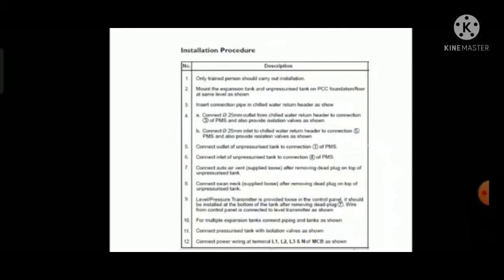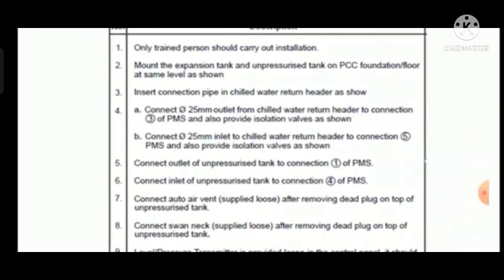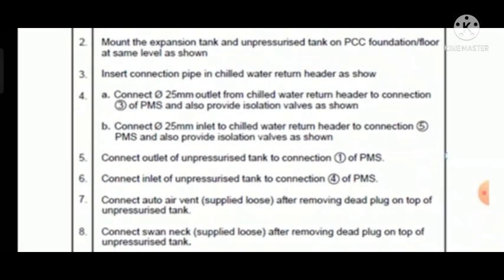And some points on the installation procedure. It is also in the installation manual provided, but anyway, I will just read it out once again for you. It should be done by a trained person, to avoid any inconveniences. Mount the expansion tank, that is the pressurized tank, the unpressurized tank, and the pumping set on PCC as in the figure. The connection pipe should be done as shown in the figure. The tapping size is 25 mm as explained. Also the numbering is mentioned on the pump: 1, 2, 3, 4, 5. So 1, 2, 3 are on the left hand side of the pump, and 4 and 5 are on the right hand side.